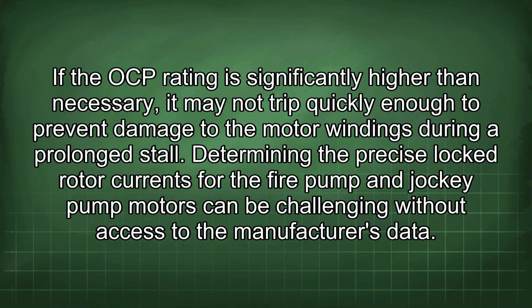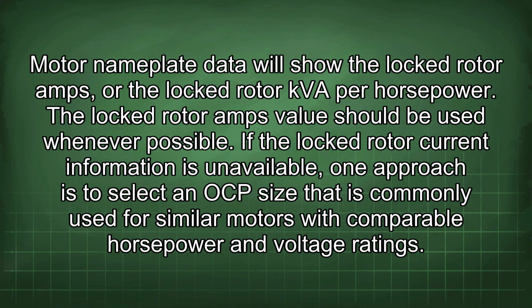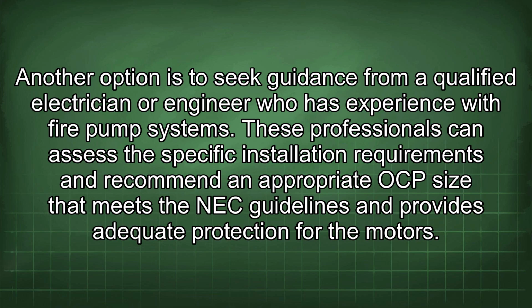Determining the precise locked rotor currents for the fire pump and jockey pump motors can be challenging without access to the manufacturer's data. Motor nameplate data will show the locked rotor amps, or the locked rotor kVA per horsepower. The locked rotor amps value should be used whenever possible. If the locked rotor current information is unavailable, one approach is to select an OCP size that is commonly used for similar motors with comparable horsepower and voltage ratings. Another option is to seek guidance from a qualified electrician or engineer who has experience with fire pump systems. These professionals can assess specific installation requirements and recommend an appropriate OCP size that meets the NEC guidelines and provides adequate protection for the motors.